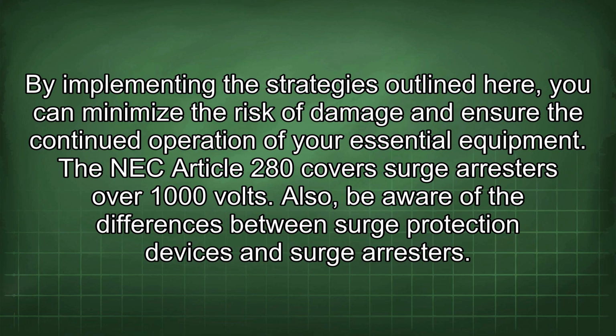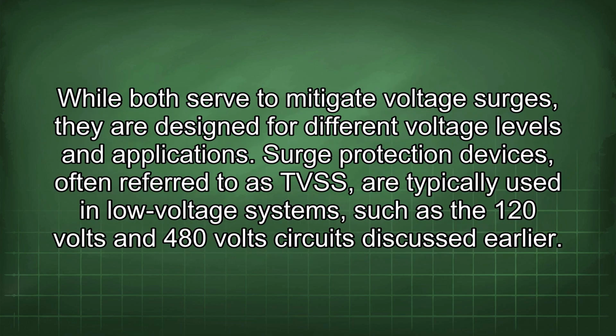The NEC Article 280 covers surge arresters over 1000 volts. Also, be aware of the differences between surge protection devices and surge arresters. While both serve to mitigate voltage surges, they are designed for different voltage levels and applications. Surge protection devices, often referred to as TVSS, are typically used in low-voltage systems such as the 120 volt and 480 volt circuits discussed earlier.